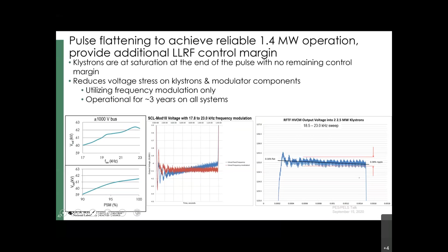The only problem with the phase shift modulation, though, is the losses on the right-hand side of the bridge got to be quite high once you dropped below about 95%. That was shown in the previous graph. You could see where that really took off. So we actually ended up just using frequency modulation, and you can see the results here for a couple of cases, the red waveform and the blue waveform over here. These are really blown up, so that's why it looks kind of bad, but in reality it's actually quite good. Those have been in operation now for a number of years, and it's really helped the RF guys out immensely.